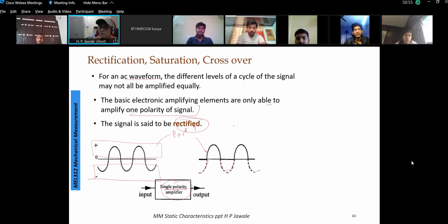This is one of the deficiencies that has been incorporated into the system, called a static characteristic. This will remain permanent over the full range of the measurement. Say for example, your pressure measurement device at some phase consists of this kind of amplifier, and if the amplifier is not carefully designed and has some error like this, it will always show some reading amplified and shown on the display panel, but the remaining signals will not be shown. So that is called a rectification error.